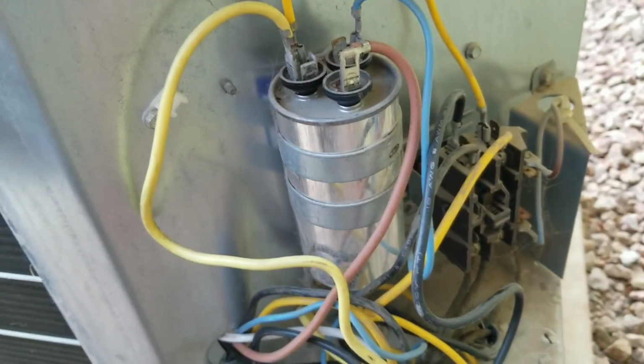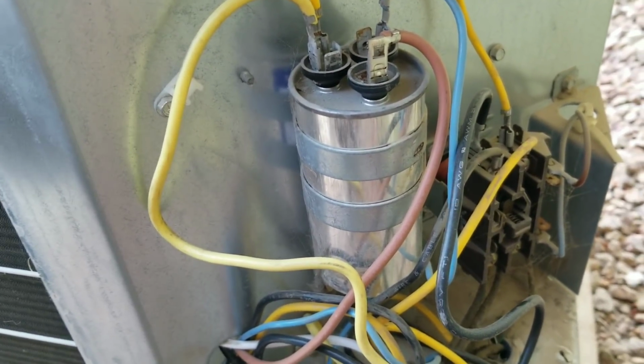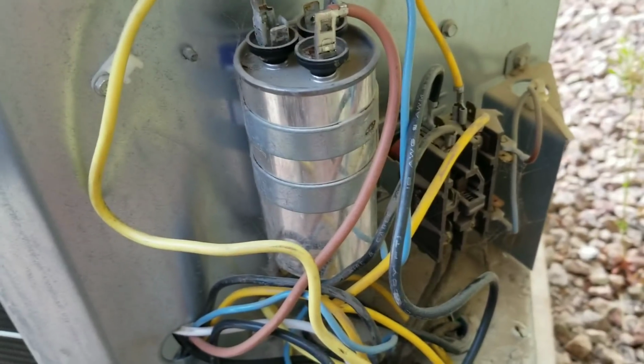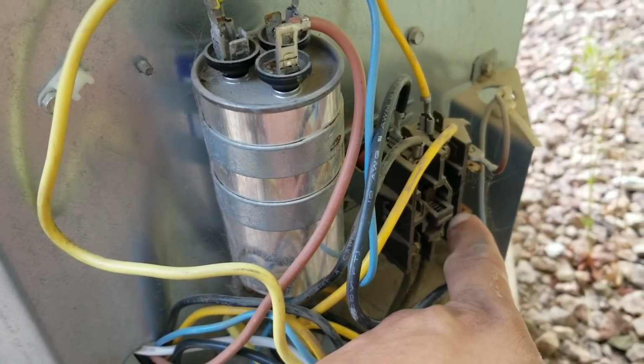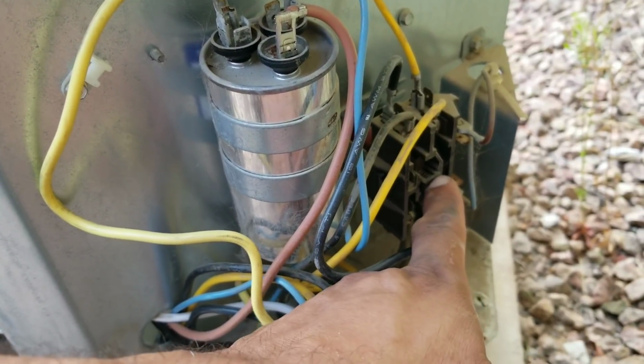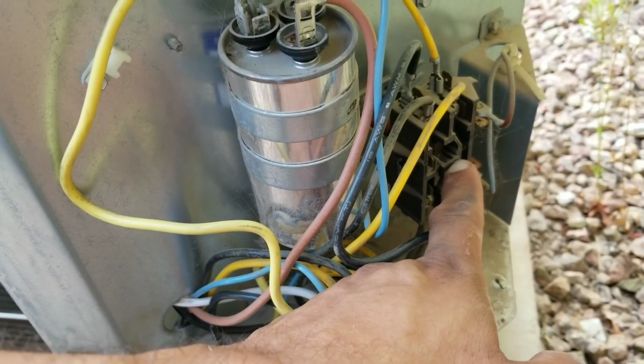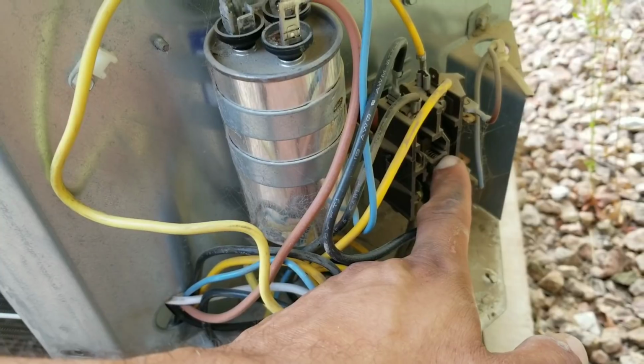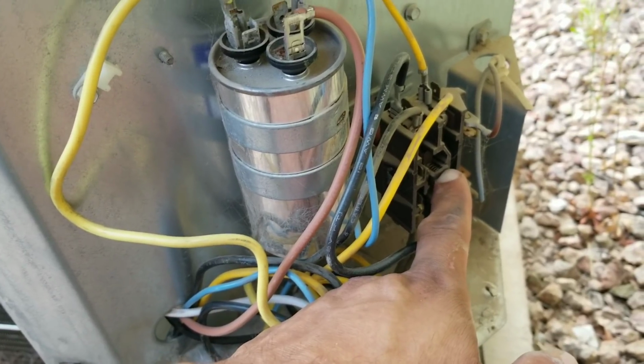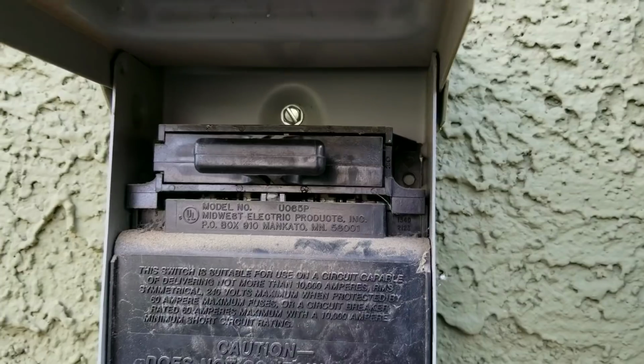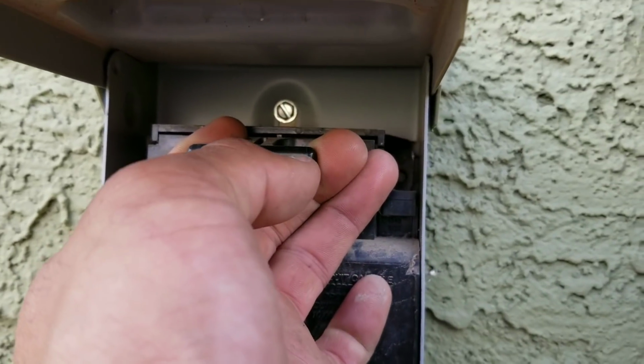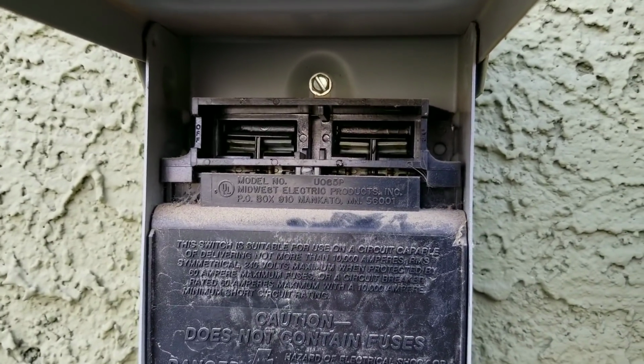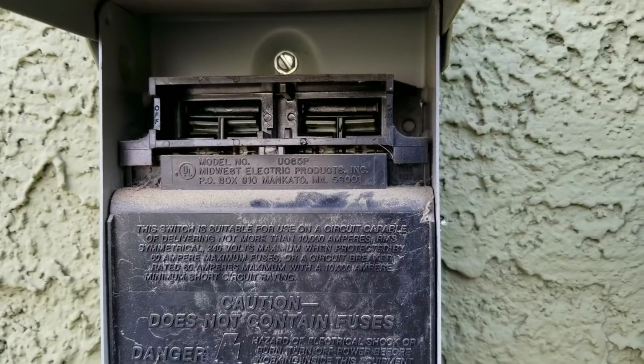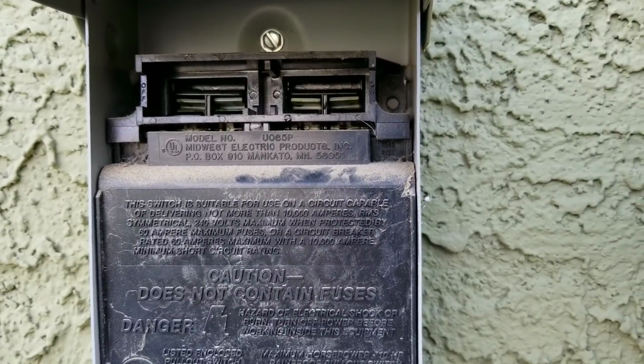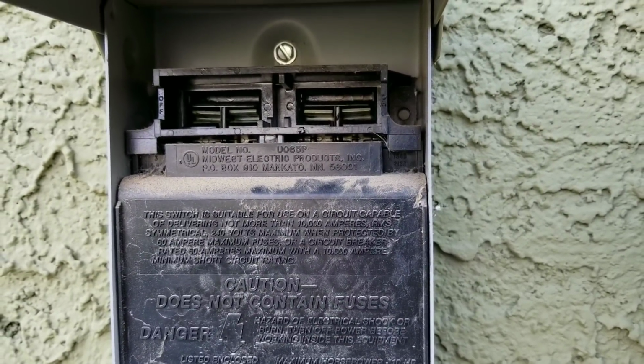First thing I always tell my guys when they're working on any AC condensing unit is to come to the side panel and press the contactor. You can see that as soon as I engage the contactor, my system does turn on. I'm going to pull my disconnect. My thermostat right now is on cool and auto, and I did lower the temperature to 75.